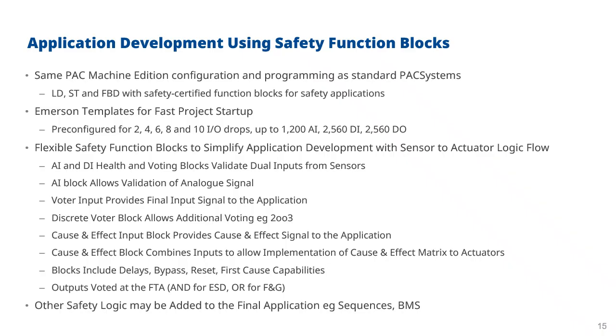There's a discrete voter block, which allows for that additional voting logic, for example, 2 out of 3 or more. And then there are cause and effect input blocks, which can implement a cause and effect signal into the application. And then we have a cause and effect block, which allows you to combine all of the cause and effect input blocks to allow implementation of the actual cause and effect matrix itself to the actuators. These blocks include delays, they include bypass functionality, they include reset capabilities, and they include first cause recording as well to allow you to understand what was the first thing that actually went wrong and caused the trip of the plant.